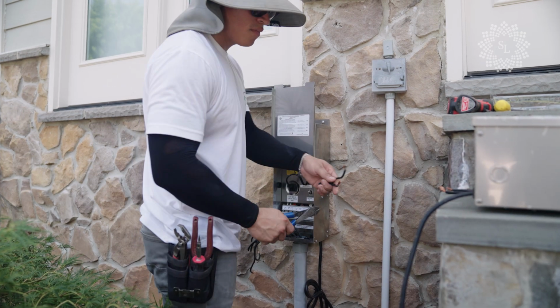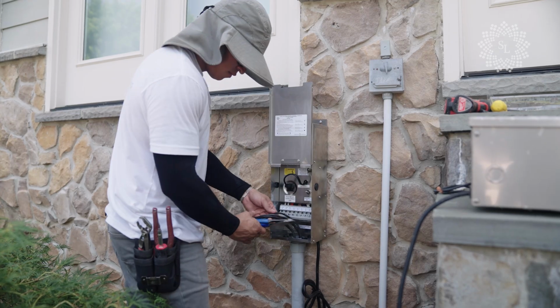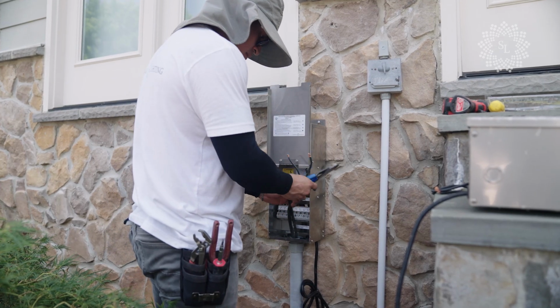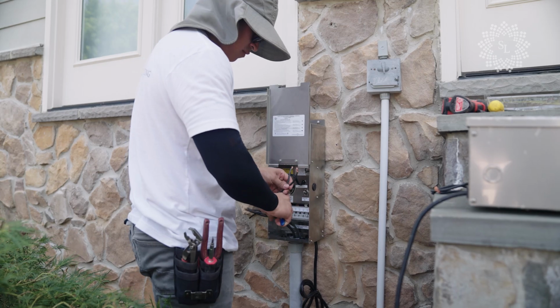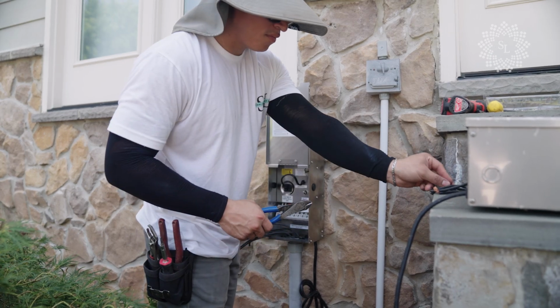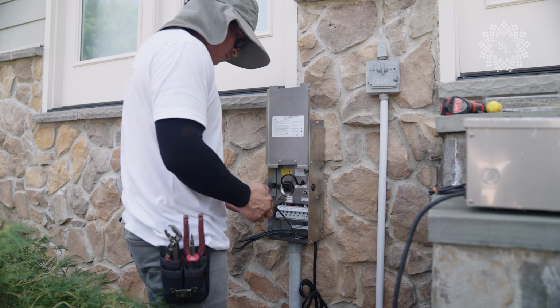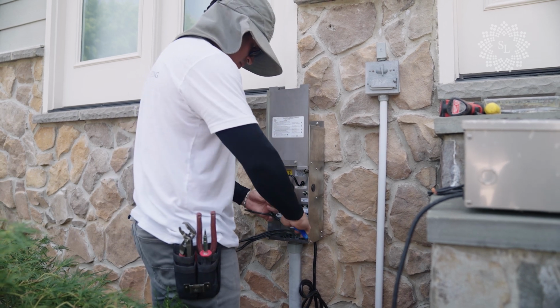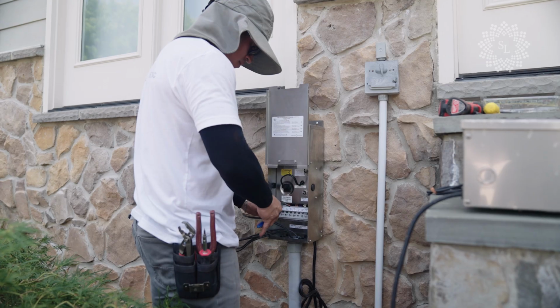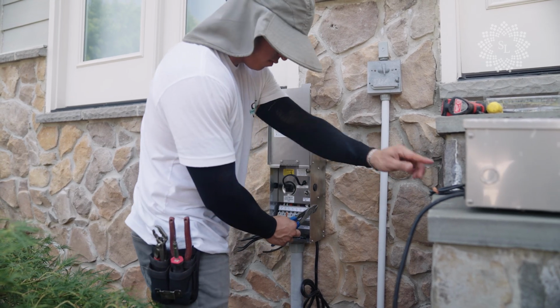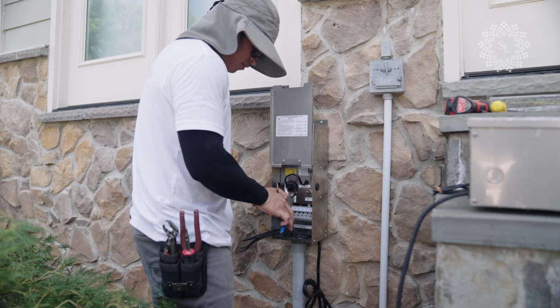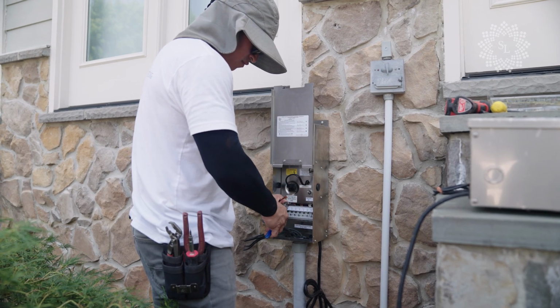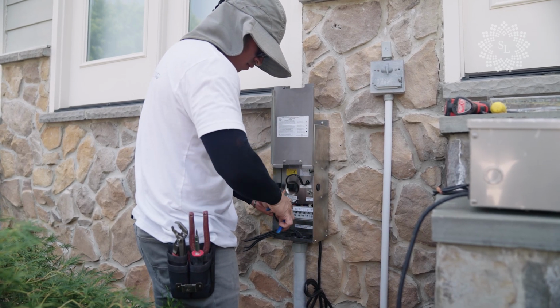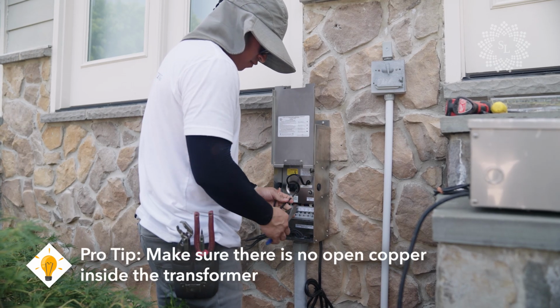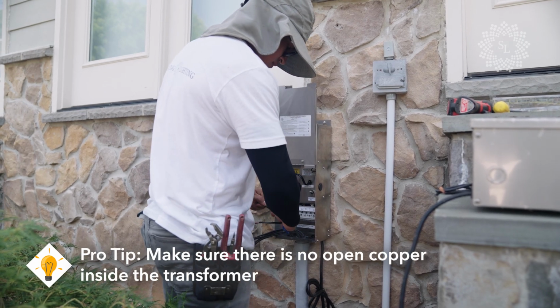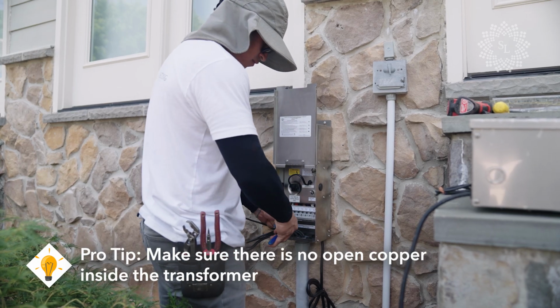Right now Danny is trimming off the old copper, the old connections, so we can have some fresh copper in our lugs. They're also a little long for the transformer, so we don't have a lot of slack inside. He's going to strip back about 3/4 inch to an inch. One thing he's going to do is make sure there's no copper showing underneath the lug, because that's where you can run into issues if you have open copper in your transformer.